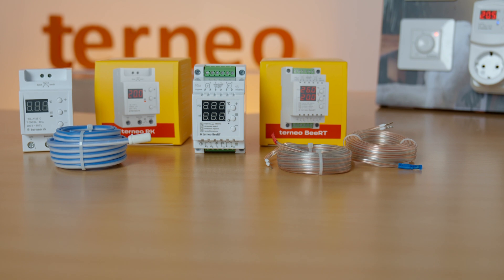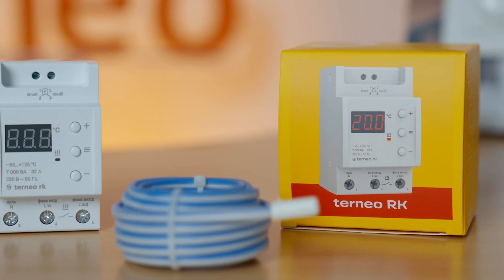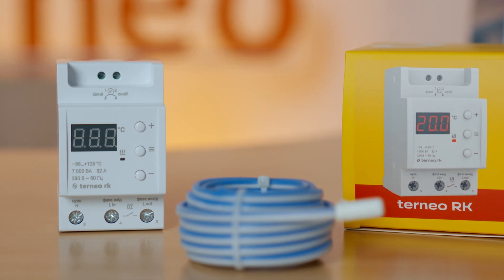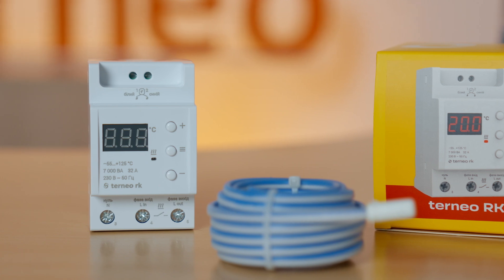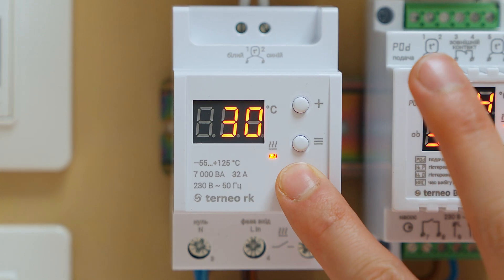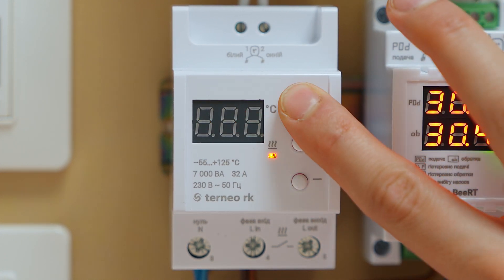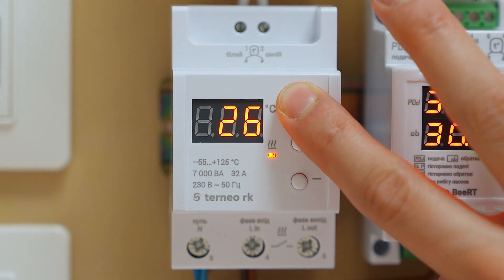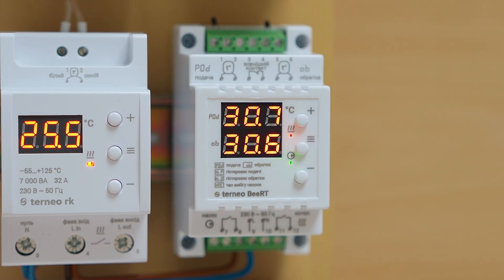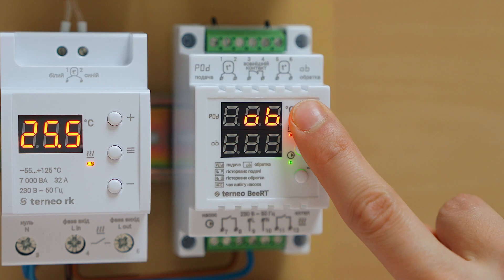Moving on to the third group – thermostats for electric boilers. Here we have two models: terneo RK and terneo BeeRT. terneo RK is a versatile model used for many tasks. It is often used to maintain a stable and consistent temperature in pipeline systems, sewage systems, and greenhouses. It can also be used to maintain a stable function of a high-capacity boiler or for upgrading an old electric boiler. This model has one of the biggest operating ranges – from minus 55 degrees Celsius up to plus 125 – and is designed to work with systems of up to 7 kW. The terneo BeeRT thermostat is designed for electric heating boiler manufacturers and operates according to data from two temperature sensors: feed and return.